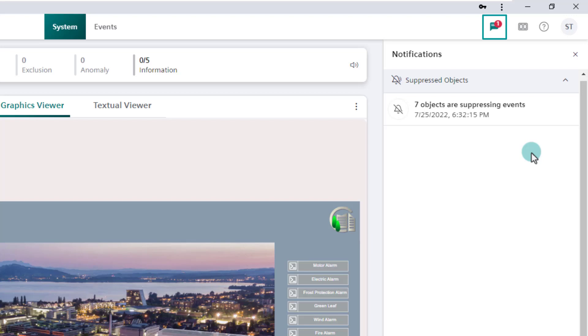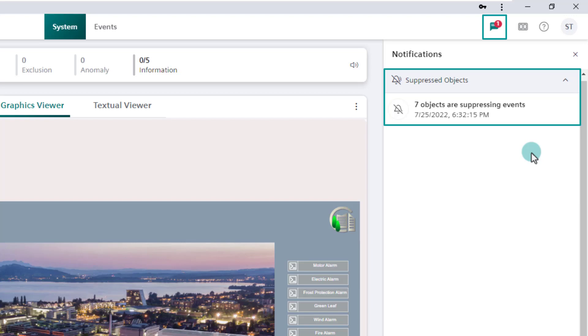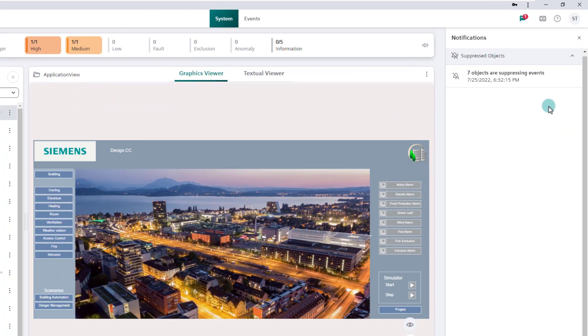Here, as an example, we are notified that the events of 7 objects are suppressed. This counter is reset every time the Flex Client application is started. After logging in, the new events are counted individually. This means that the events since the last log off are combined into a group with the counter one, and, as can be seen in our example, alarms are suppressed for 7 objects.